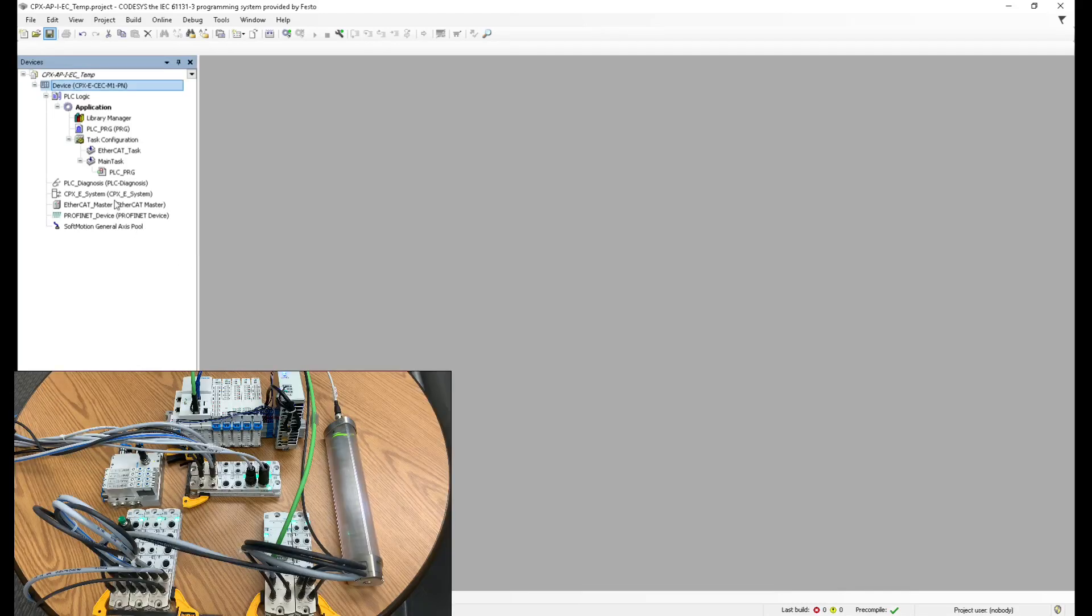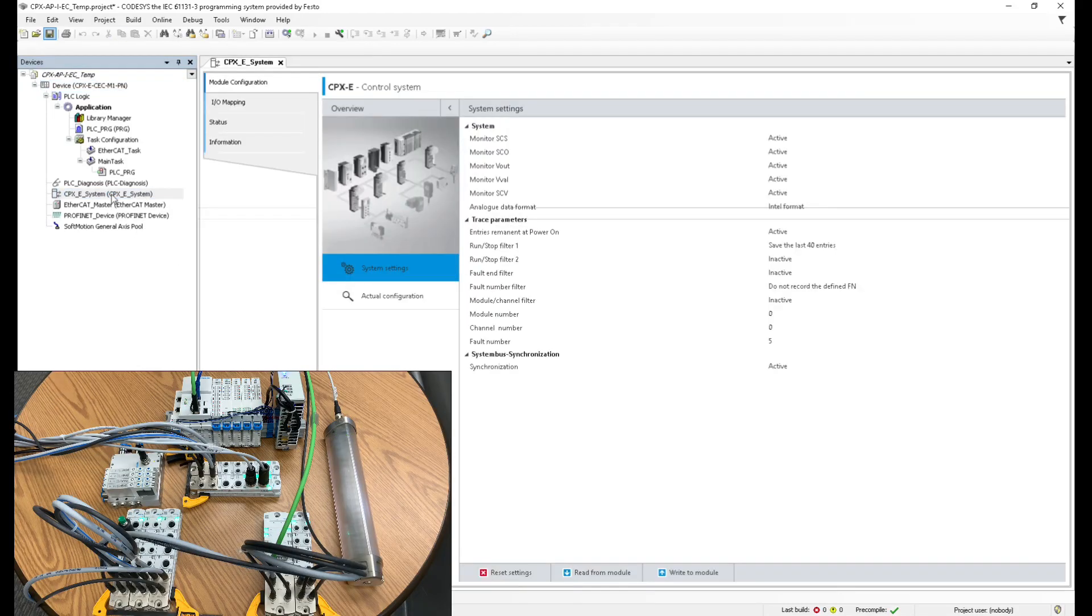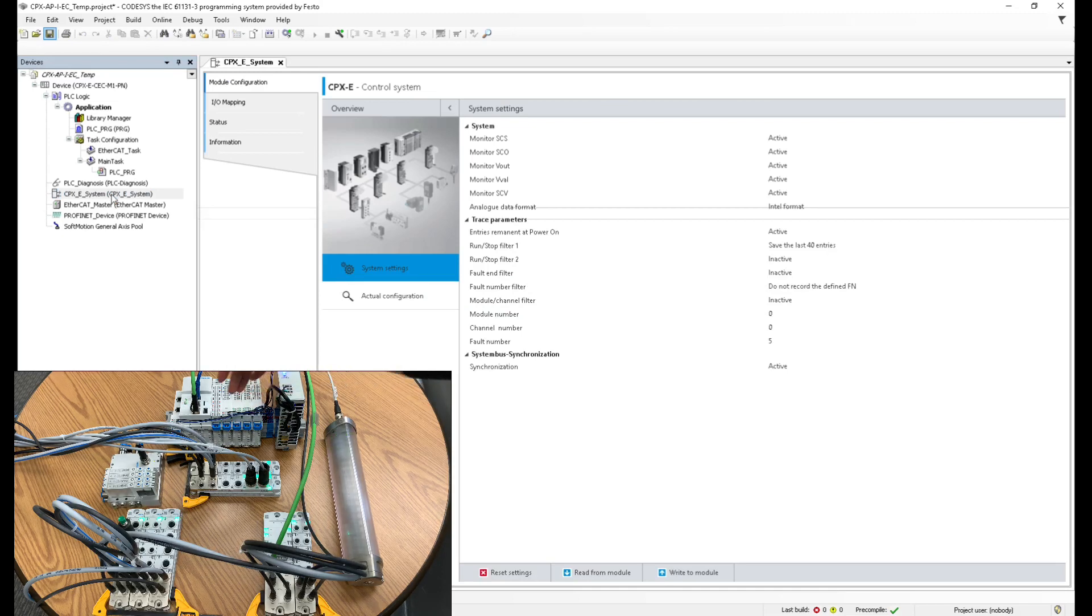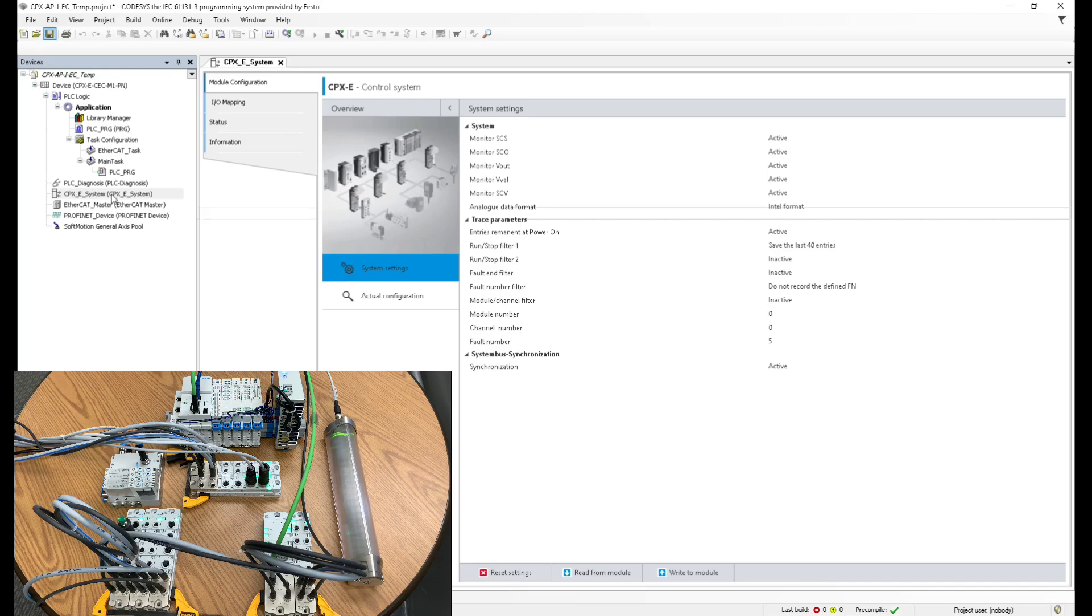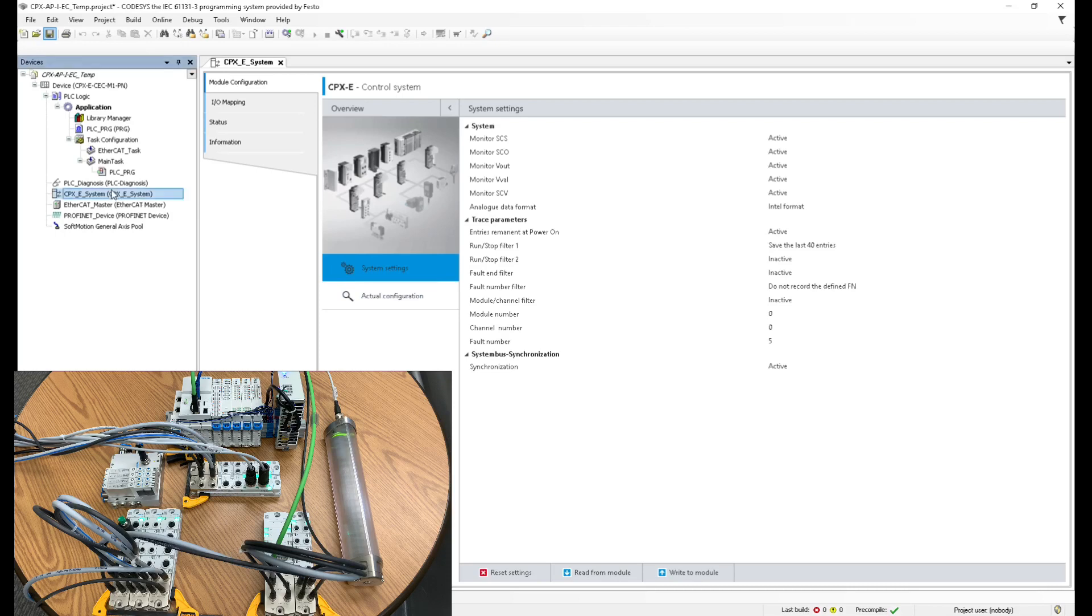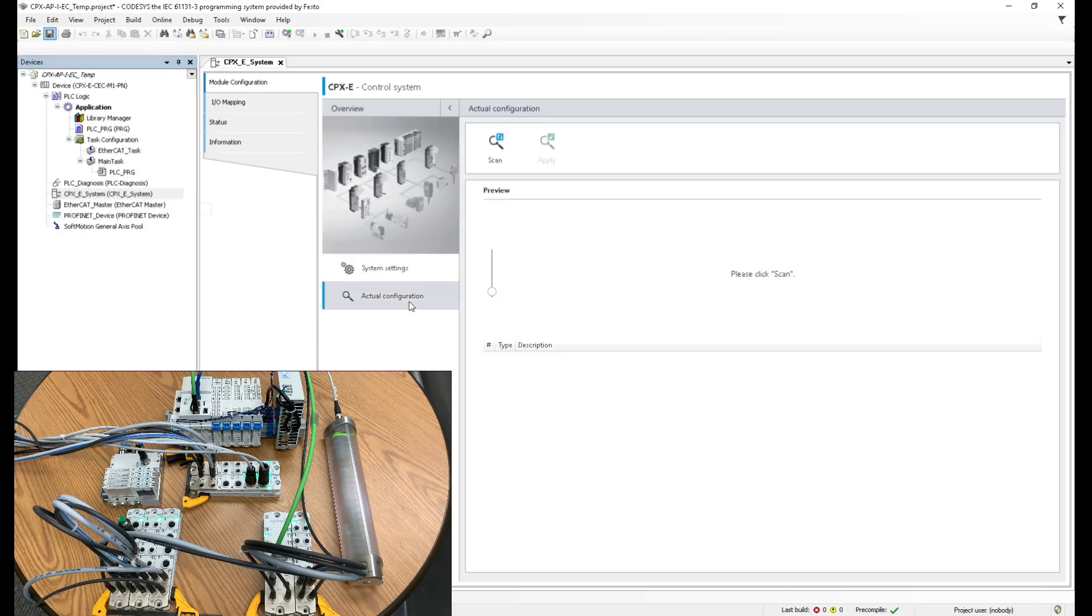I'm going to close this. And then the next thing I'm going to do is check the IO on board. This is configurable. I could add more slices to it or remove slices. Since it is configurable, I want to see what's the actual configuration. So I'm going to click here, cpxe system, and then actual configuration, and then scan. Since I already established my path, I can just scan and this immediately pulls the configuration from the actual hardware.